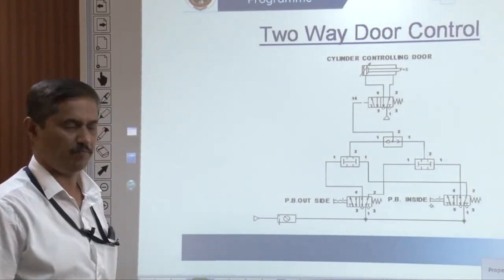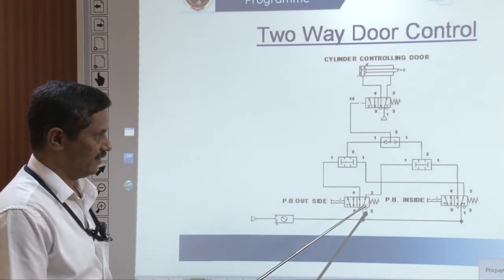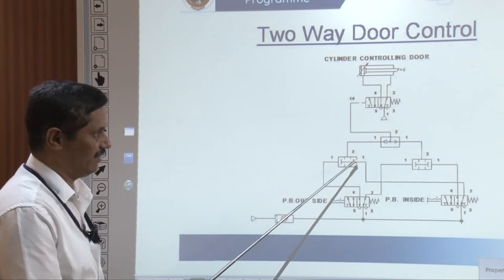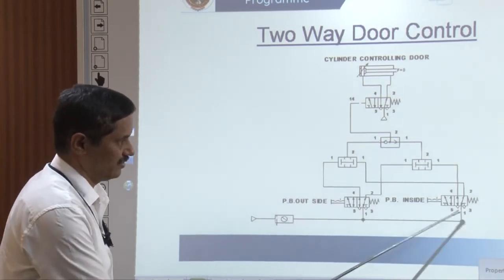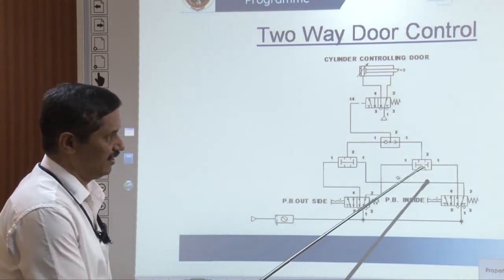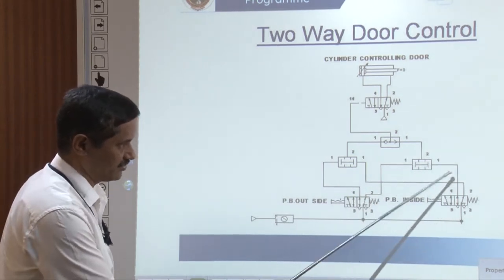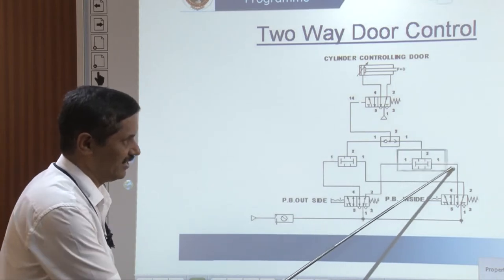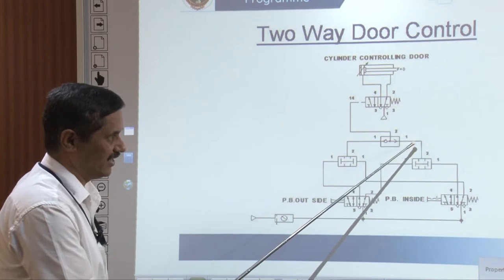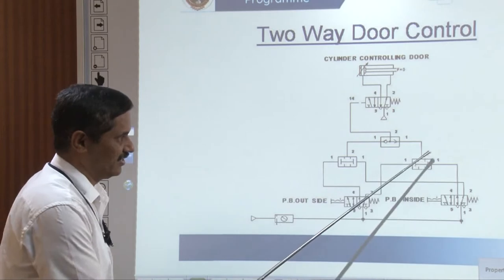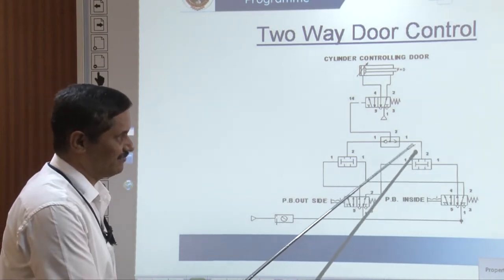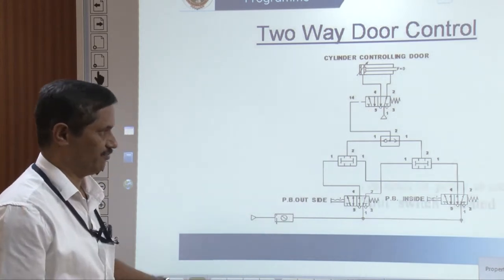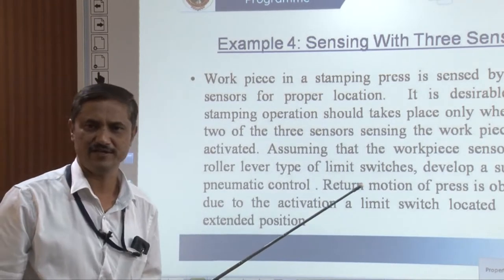If I show a symbol like this, this can hold the position. You press this and air will come from here to here. If any one of these is pressed, the air will come here. There is an AND logic created between these two. Similarly, there is an OR valve — when in the conventional position, you are also getting a signal here to this valve. In both conditions, pressed or without pressing, you have an enabler so that any one of these signals is available, resulting in opening or closing of the cylinder — moving it to and fro.